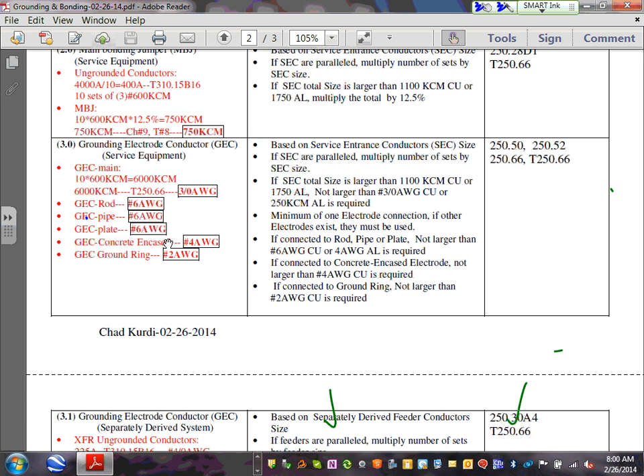So, grounding electrode conductor, gentlemen, at the service, look what happens. You size it based on the service entrance conductor, and you have to go to 250.66, like you guys know that. You don't have to go larger than 3 aught. Can you guys see that? 3 aught is the maximum for grounding electrode conductor. And minimum of one electrode connection. If others exist, you must tie to it.